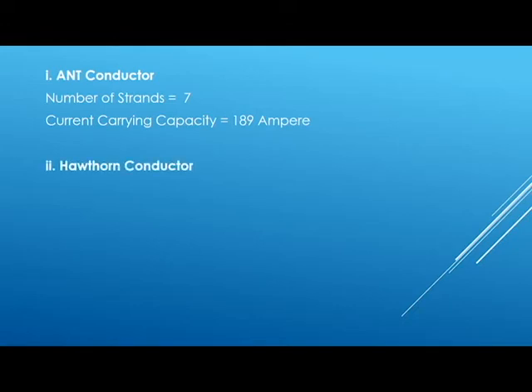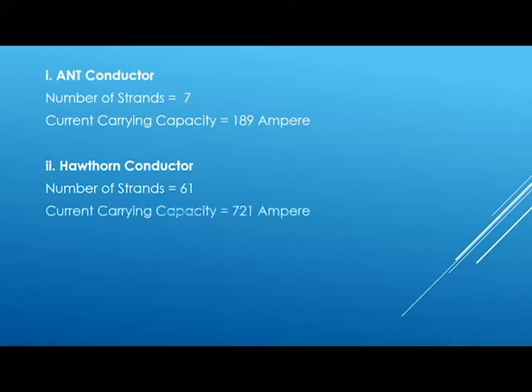The current carrying capacity of the Ant conductor is 189 amperes. Next is the Hawthorn conductor — the number of strands is 61 and its current carrying capacity is 721 amperes. Third is the Arbutus conductor — the number of strands is 37 and its current carrying capacity is 546 amperes.